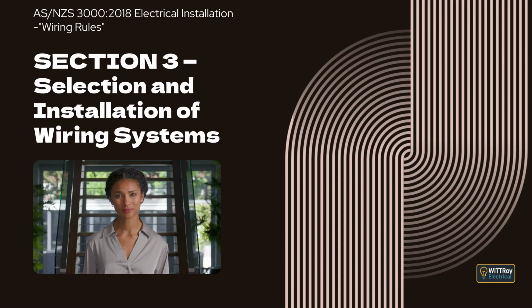Clause 3.3.2.4 Solid foreign bodies. This clause means wiring systems must be selected and installed to reduce the entry of solid objects during installation, use and maintenance. Where dust or other substances may be present in large amounts, extra precautions must be taken to prevent build-up that could reduce heat dissipation.